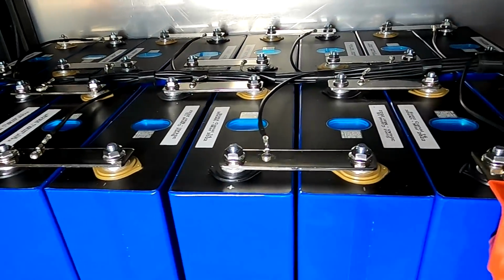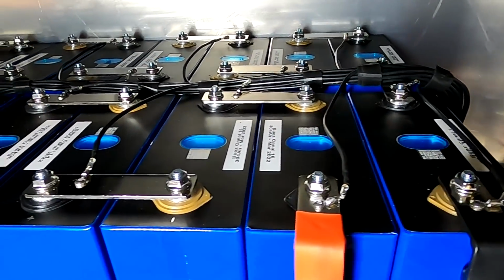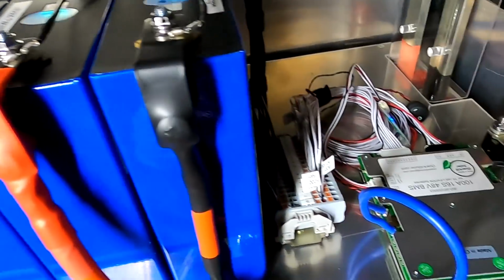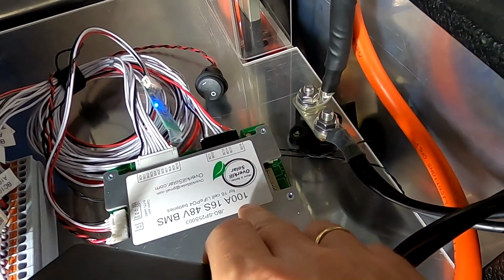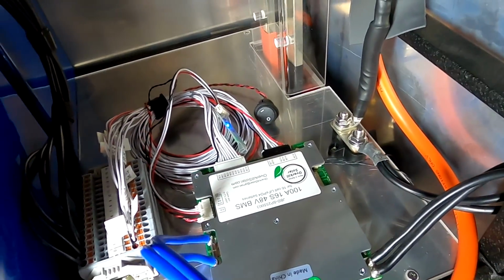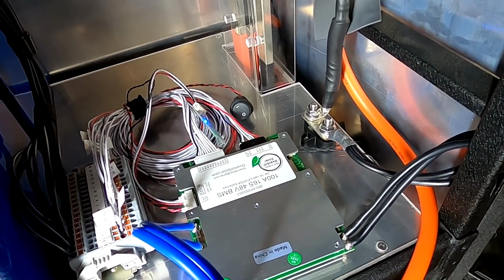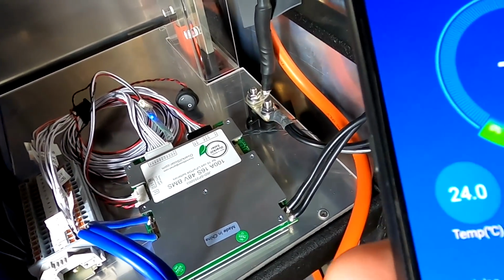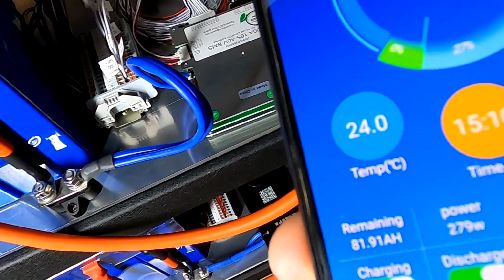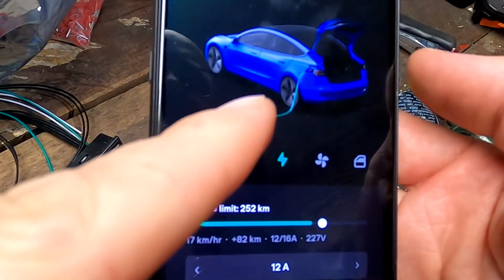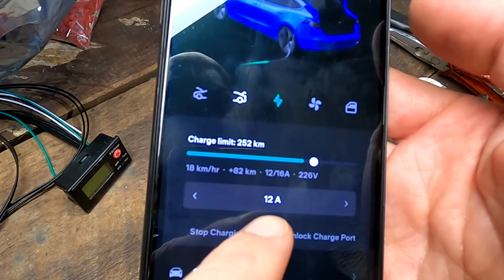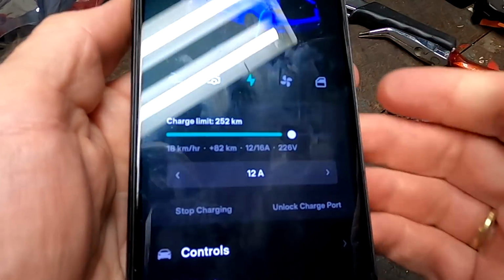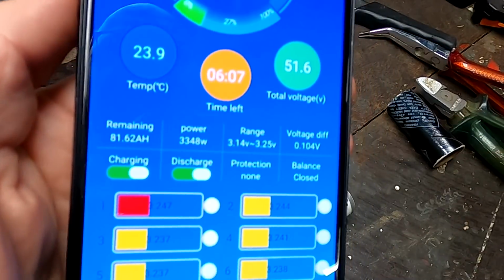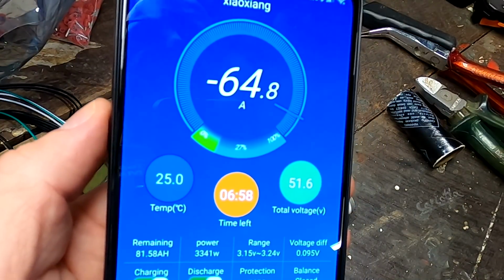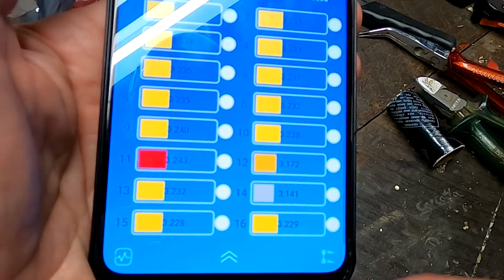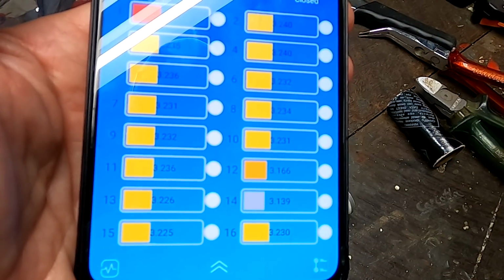So we do a little infrared camera test and see if we can observe any hotspots here on the battery. And also we have to remember this is only a 100 amp BMS, so that's the maximum we can pull, around 5 kilowatts from this battery. So let's do it. As always, we're using the Tesla as our load, charging with 12 amps at the moment, and I just want to have a look. There's 64 amps. We have to keep an eye on 12 and 14.